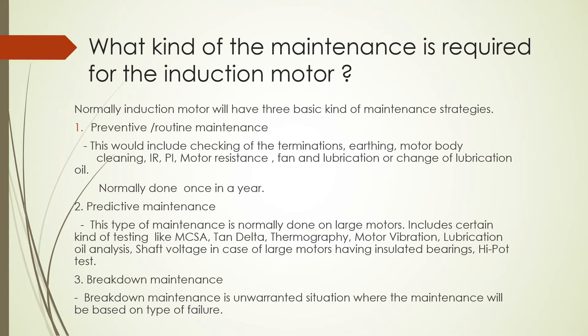The first question: what kind of maintenance is required for an induction motor? Induction motors normally have three basic maintenance strategies. Preventive or routine maintenance includes checking of terminations, earthing, motor body cleaning, insulation resistance (IR) checking, polarization index (PI) checking, winding resistance checking, fan and lubrication — including change of lubrication oil. Normally this routine maintenance is done once a year.